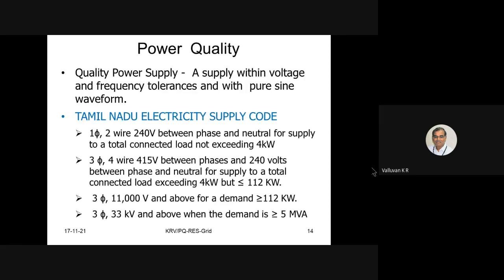From here, we move on to the next concept of power quality. Quality power supply is defined as a supply within voltage and frequency tolerances with pure sine waveform. In Tamil Nadu, the electricity supply code says single phase 2-wire 240 volt, 3-phase 4-wire 415 volt, 11 kilovolt and above for industrial requirement, 3-phase 33 kV and above for 5 megawatt demand, etc. So all these things are standardized all over the country, all over the world.